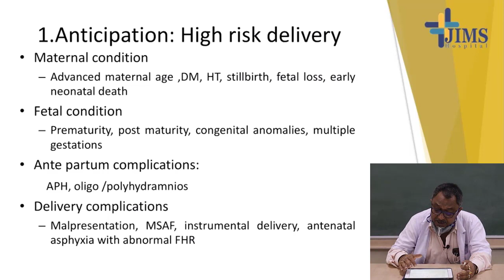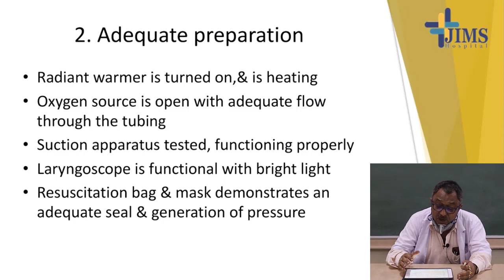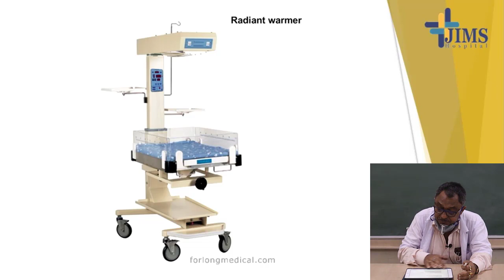Now, adequate preparation is required. Radiant warmer is to be turned on and the room should be heated. Oxygen source should be there with open and adequate tubings. Suction apparatus should be tested and functioning properly. Laryngoscope should be functional with bright light. Resuscitation bag and mask should demonstrate an adequate seal and generation of pressure. Now this is a picture of a radiant warmer.